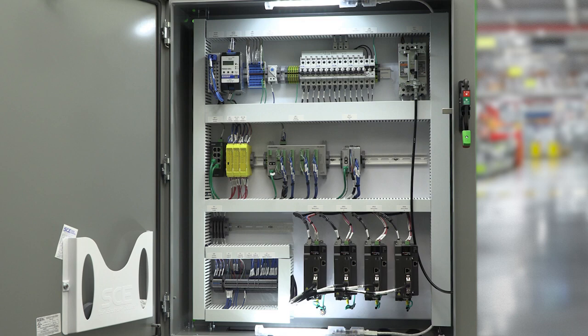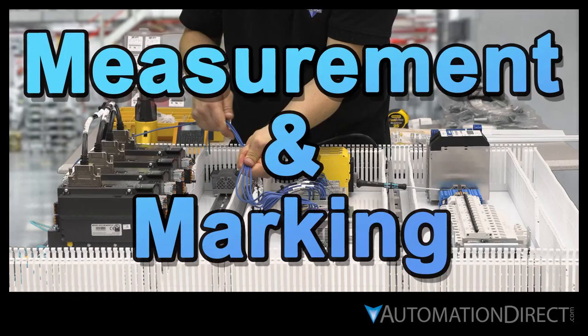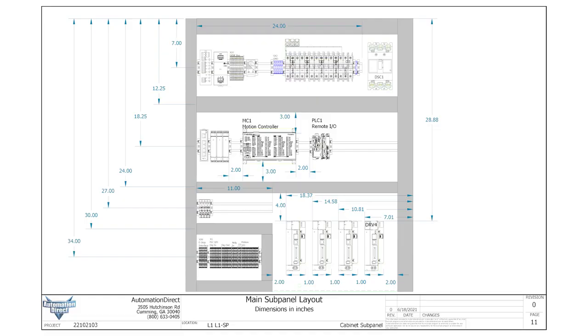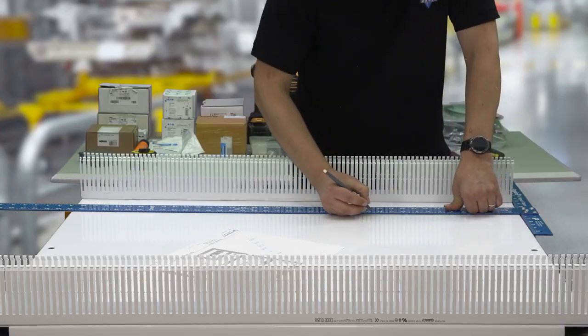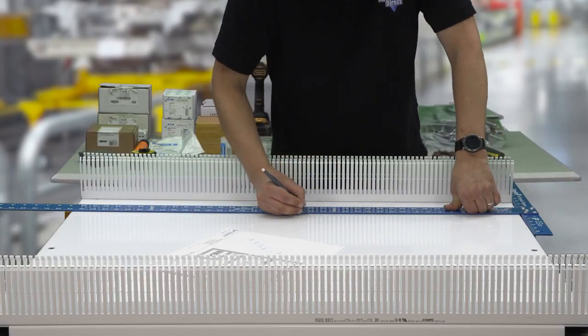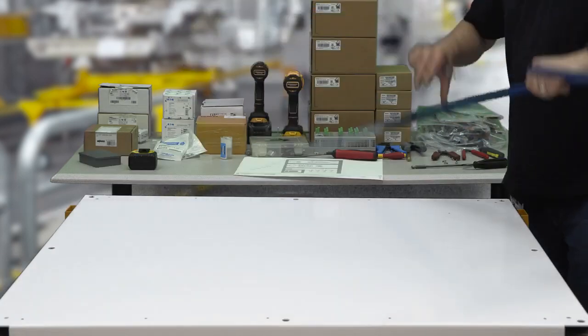This is done so these parts don't overheat under heavy load. Now that the decision where everything goes on our control panel has been made, it's time to mark the lines and plan the holes. Using a T-square and a mechanical pencil, measure and mark the lines where the DIN rail and wire duct will be installed.